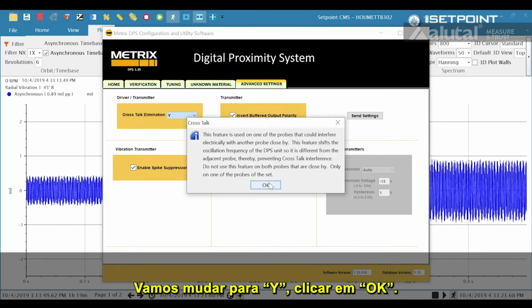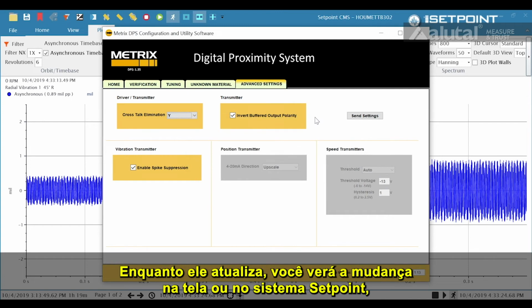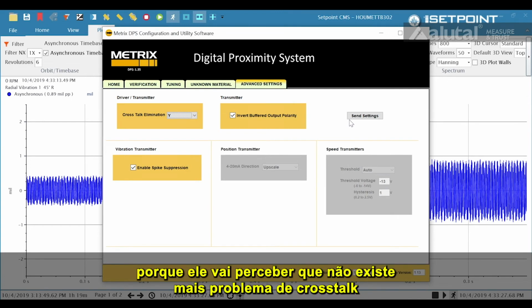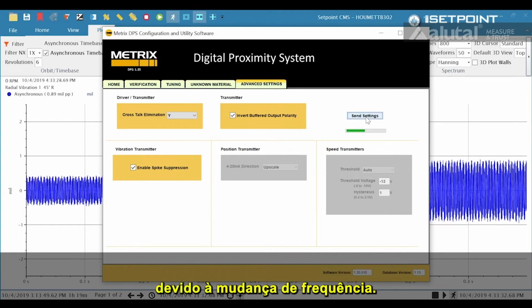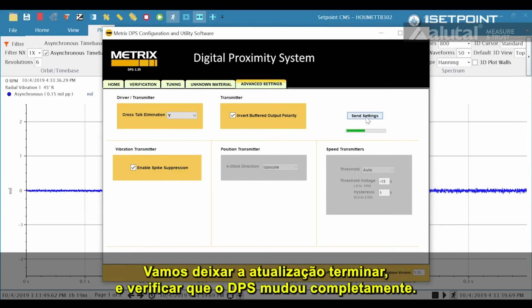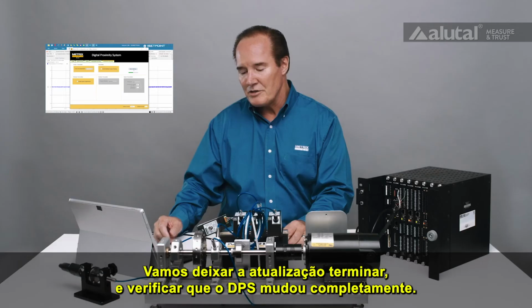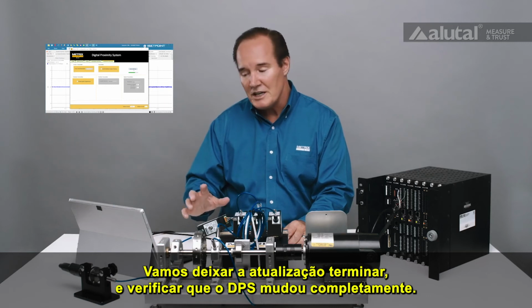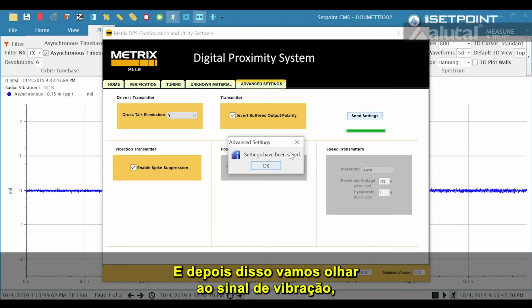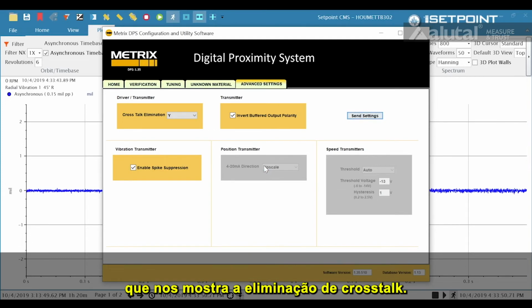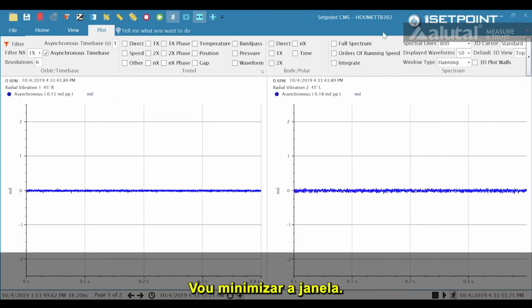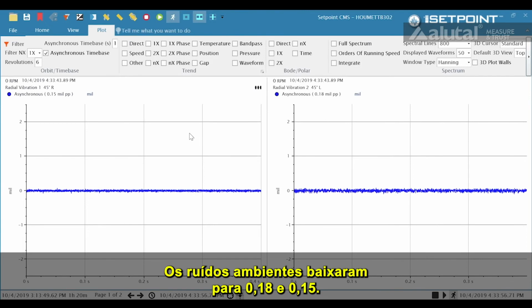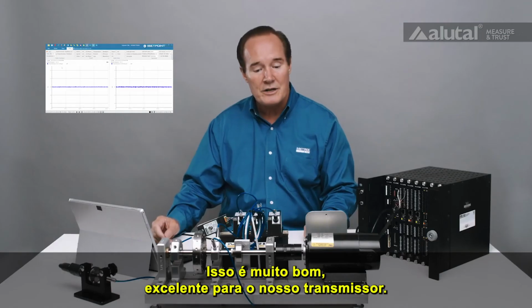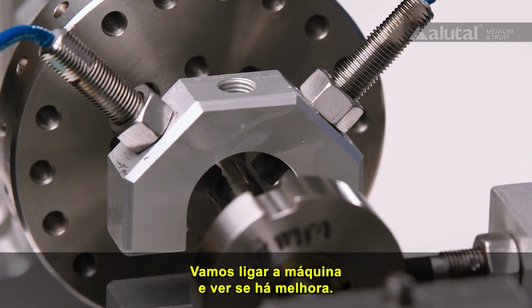And we'll say OK. And right as it updates, you'll start to see a change in the screen in the set point system, because it's going to basically sense that we don't have this crosstalk problem anymore because we've shifted the frequency. And you can see how it's updated. We'll let it finish updating and make sure the DPS is fully changed. And then after that, we'll look at the vibration signal, and that shows you crosstalk elimination. We'll minimize this. And you can see now our ambient noise level is down to 0.18 and 0.15. That's very good, excellent for a transmitter. And let's start up the machine and see if it behaves any better.